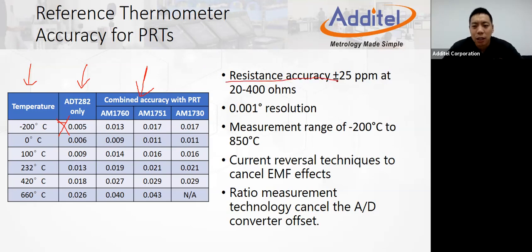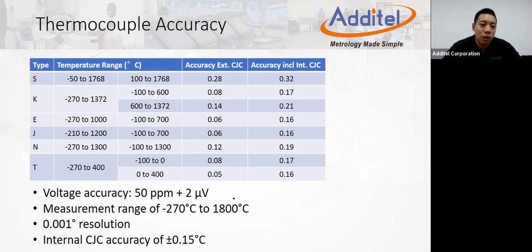For the resistance accuracy in PRT measurement, the accuracy is 25 ppm. The range is 20 to 400 ohms, covering most common PRTs and RTDs. The resolution is 0.001 degrees Celsius or degrees Kelvin, or 1 milli-K. The measurement range in temperature is -200°C to 850°C, pretty wide. We use current reversal techniques to cancel the EMF offset and improve accuracy, and we apply ratio measurement technology to cancel the AD converter offset, further improving measurement accuracy for PRT measurement.